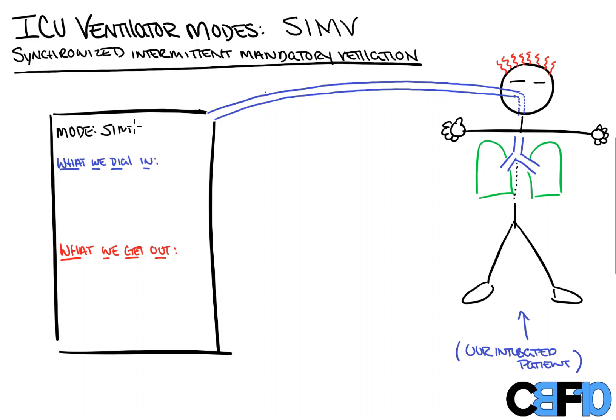So we're going to label this SIMV, and we're going to talk about in the same order: what we dial in, then how it works, and then what we're going to get out as a result. Just like in AC mode, we're going to dial in our FiO2, which is our percent oxygen. We're going to dial in our rate, also seen as F on the machine for frequency. We're going to dial in our tidal volume and our PEEP. Now there is one more thing we're going to dial in here that we didn't necessarily see on AC mode, and this is a pressure support. We'll explain what that's for during this as well.